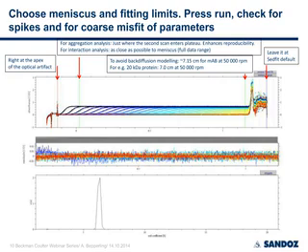So I set it here to 7.15 centimeters and leave it there. For the rest of the analysis, when I, for example, analyze multiple cells of one rotor, I choose the lower fitting limit here and leave it constant for all cells. And in the front, the upper fitting limit, I choose, as I said, at the position where the second scan enters the plateau. This gives, in my experience, the most stable analysis of the monomer, dimer, and so on fractions.